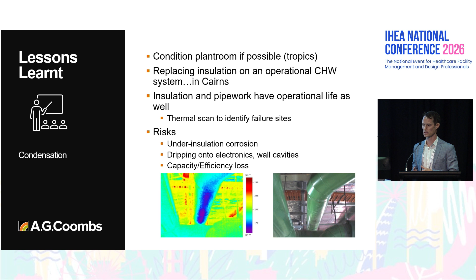So ventilation in plant rooms is a bit of a no-brainer, but I think we need to move away from having just a basic litres per second per square metre application of ventilation. Understanding exactly what equipment is going in and how much heat rejection it requires is really critical. And if that's for refrigerant clearance after a leak, then we more than likely need low-level extract, because all the synthetic refrigerants are typically heavier than air.